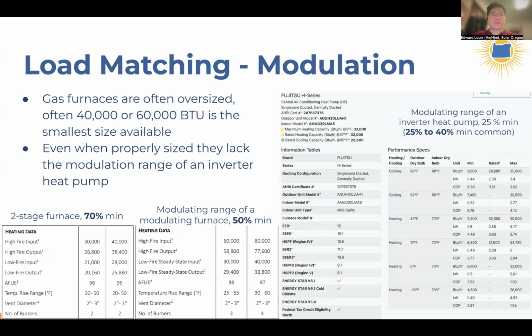So, on a mild day, sometimes even the 24,000 BTUs, for example a 2 ton heat pump, is still too much. A modulating heat pump or an inverter driven heat pump can modulate its output quite a bit. Like in this example, this 2.5 ton heat pump shown on the right hand side might have a nominal output of 2.5 tons, but it can modulate down at 47 degrees to only 9,200 BTUs.